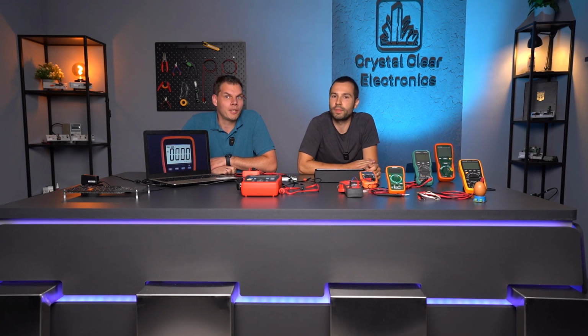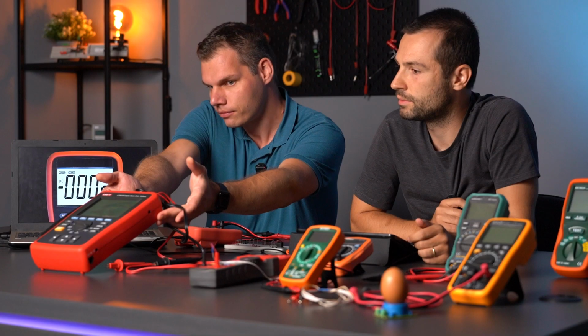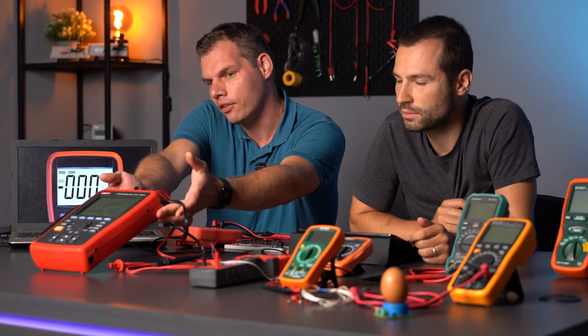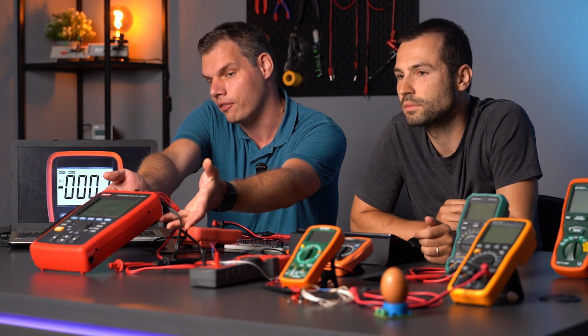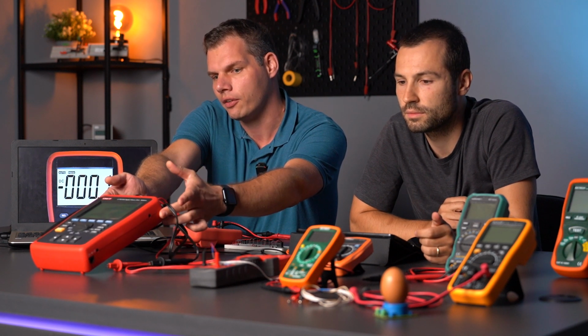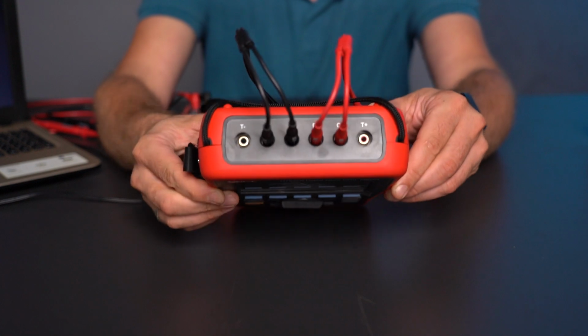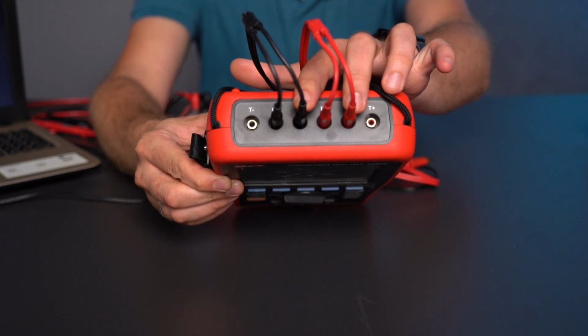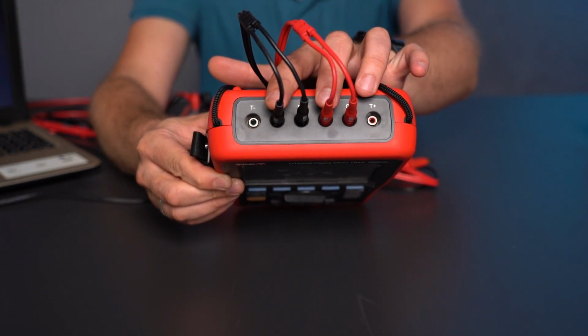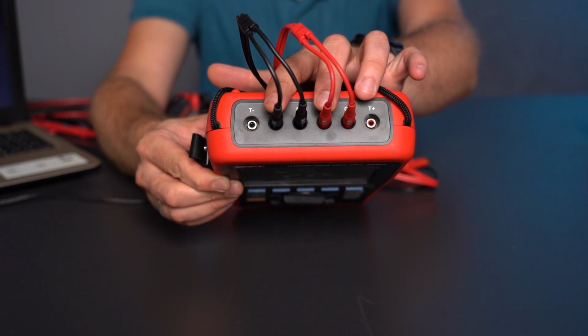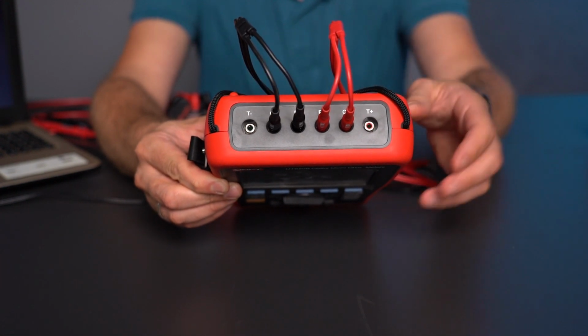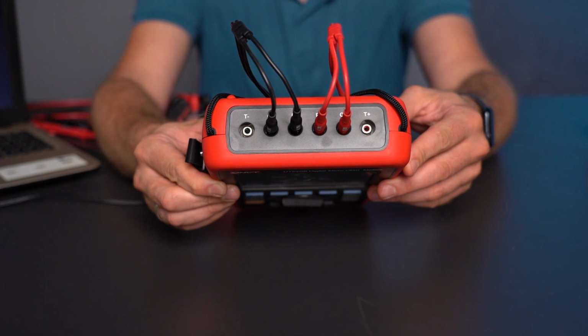Before we go into more detail about the multimeter we use, we'd like to show you a few other devices that we will only touch on. For example, here is an ohm meter for measuring the resistance of 4 wires. This is special because, as you can guess from the name, it uses 4 wires, 2 of which carry the measuring current to the resistance to be measured, and 2 of which measure the voltage across that resistance. In this way, the resistance of the measuring lead can be compensated and very small resistances can be measured.